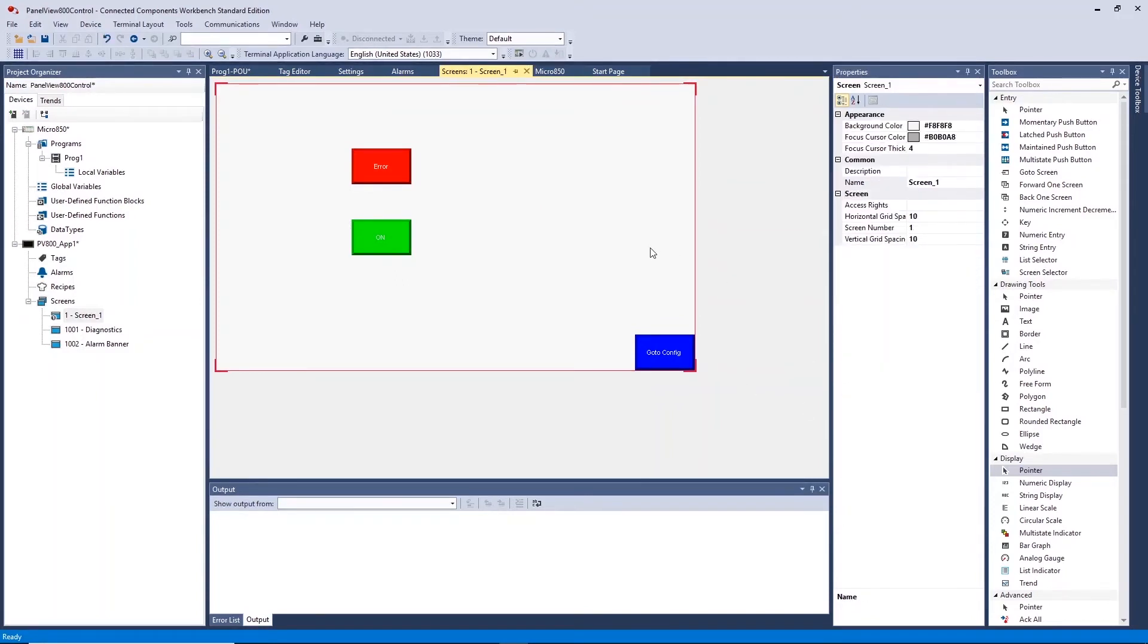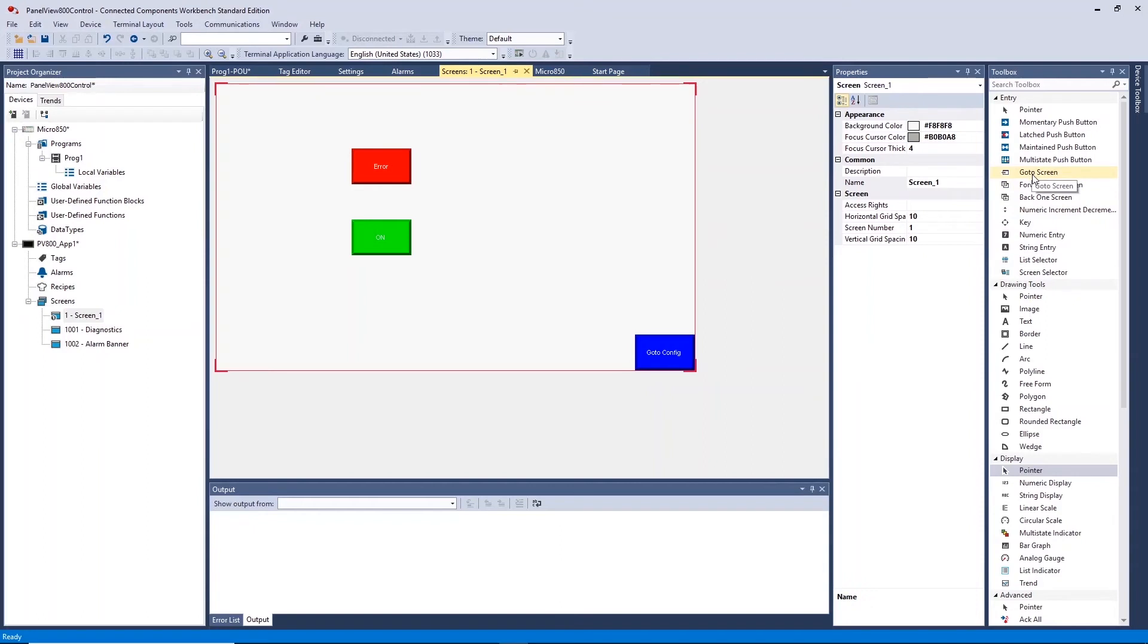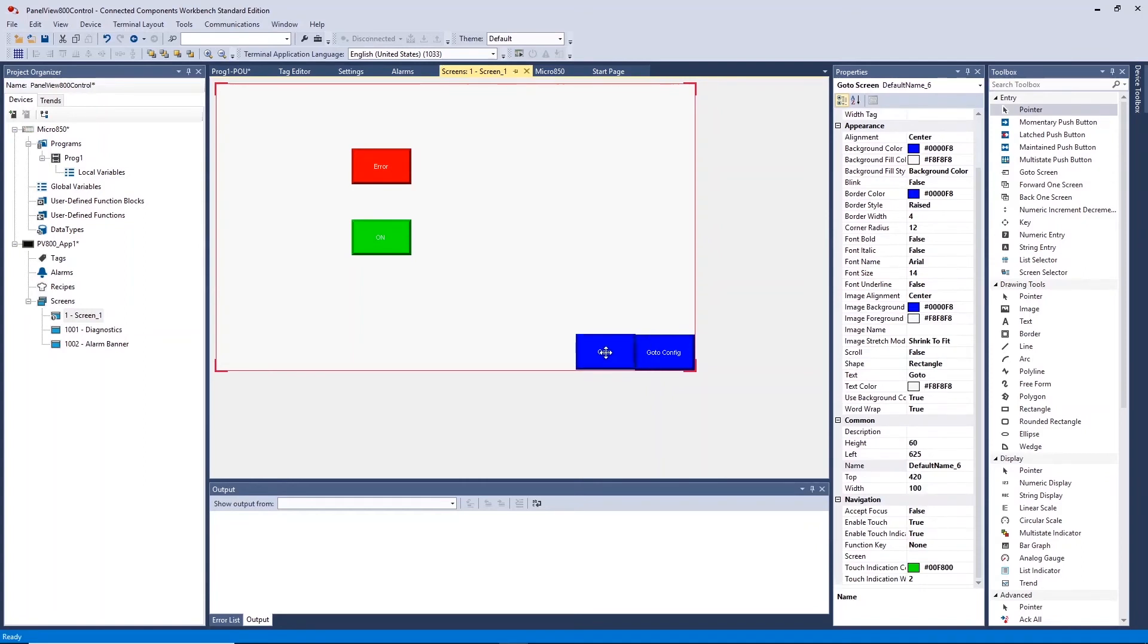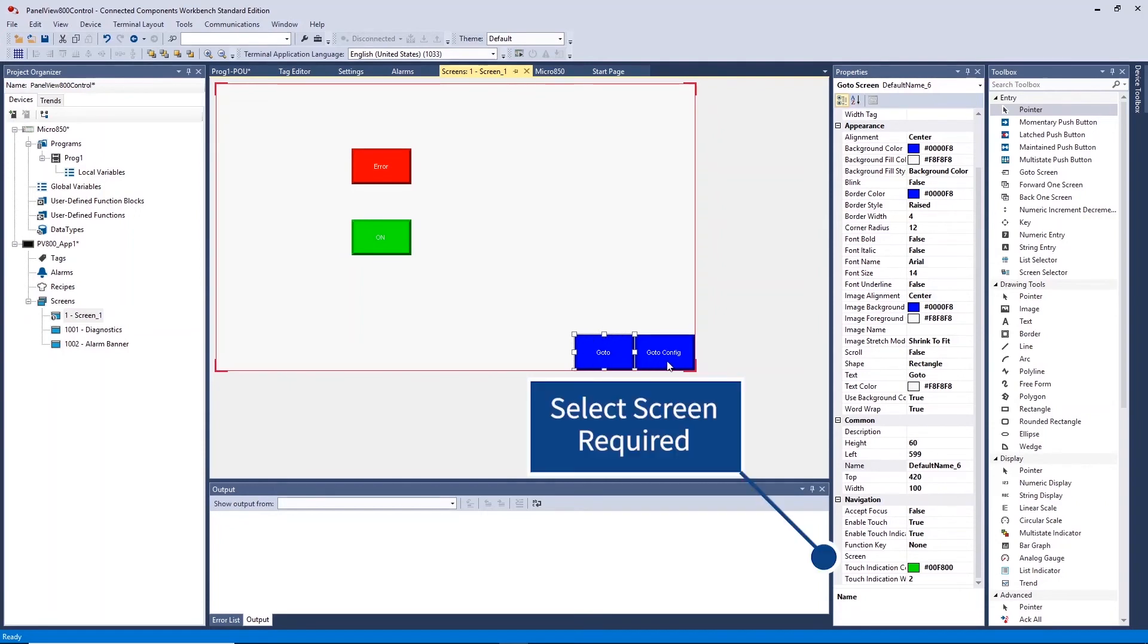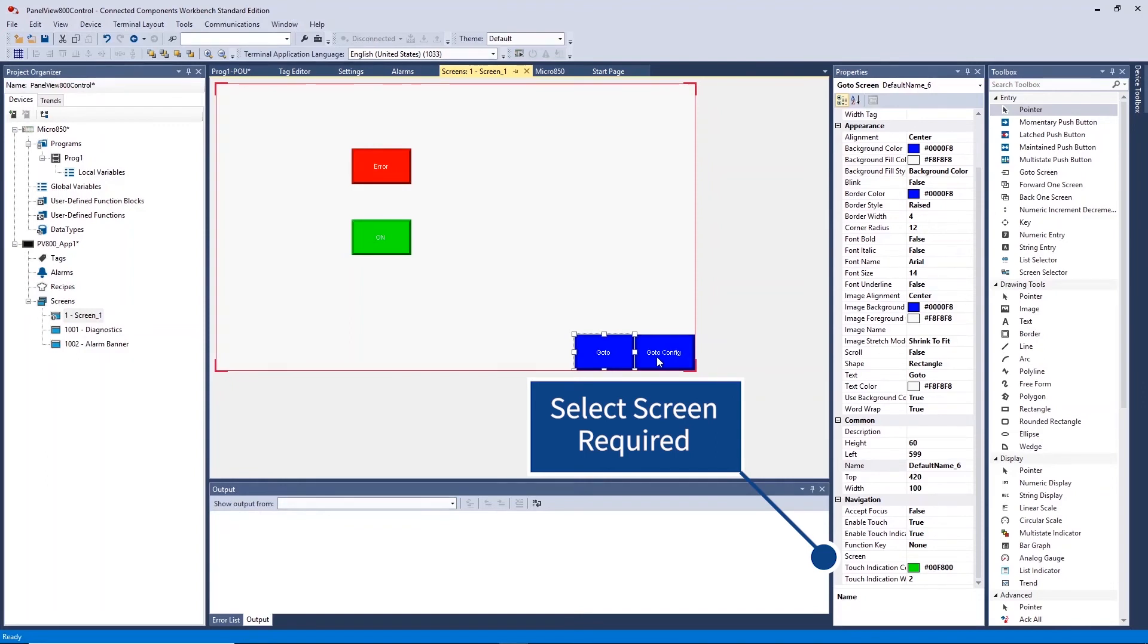To create navigation to a new page, select Go To Screen within the Toolbox and place as required. This will be required in every HMI application in order to access the terminal settings of the HMI, including HMI settings and loading of HMI applications. In Properties under Navigation, Screen allows you to choose where this will direct the user to.